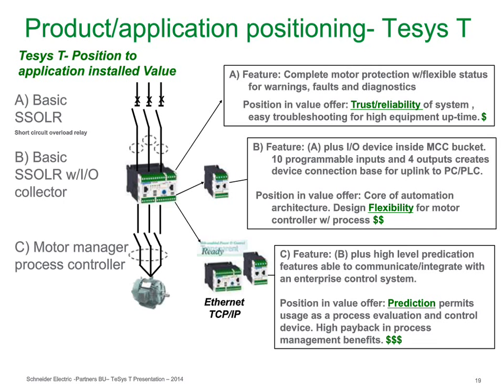And then finally, again, the idea of the motor management is, by setting norms, I can actually use the device to set predictability and set alarms separate from faults that will allow me to actually schedule maintenance based upon where I set the alarms for these devices.